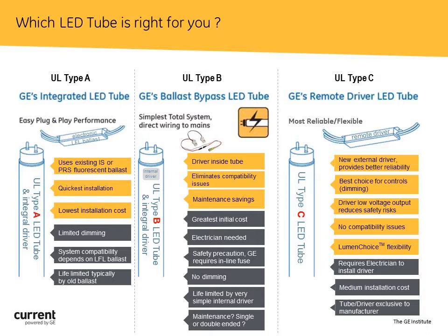on the one end. So if you're going with a single-ended type B, you have to use unshunted sockets, which means you may not only have to remove the ballast and the tubes, you may also have to rewire and buy new tombstones for your unshunted socket need. Now once again, the wiring harness that GE provides is for the single-ended, so they are unshunted tombstones.